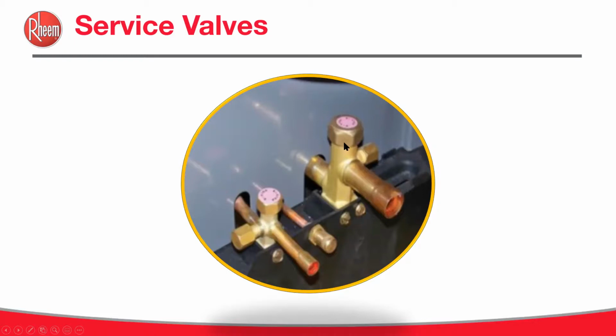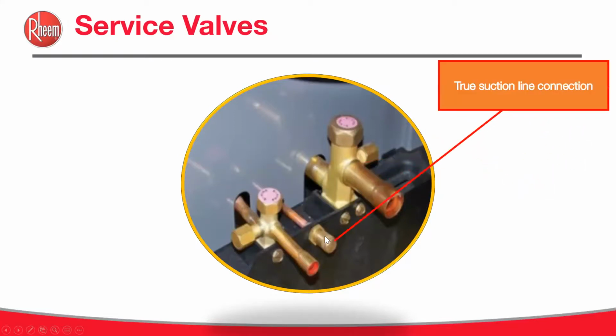For the suction one, it takes a 5/16 Allen wrench. But also notice we have this extra port. What is this extra port? Well, that's your true suction line. Again, this is only required on heat pumps. You have to hook up here for your true suction. If you hook up to here and here, when you're in heat pump or heating mode, you will find they're going to read the same. And we've had that. You have to make sure you hook up to true suction. And we've made it easy for you. We put it outside the unit so you're not having to take off a cover to get back to the compressor where there's a true suction line.